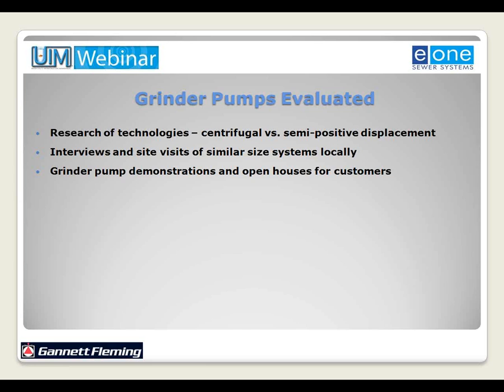Basically, there are two types of grinder pumps, the centrifugal and semi-positive displacement pump. And just briefly, centrifugal pumps, their output varies widely depending on head conditions. They're usually 1 or 2 horsepower motors with higher RPM.